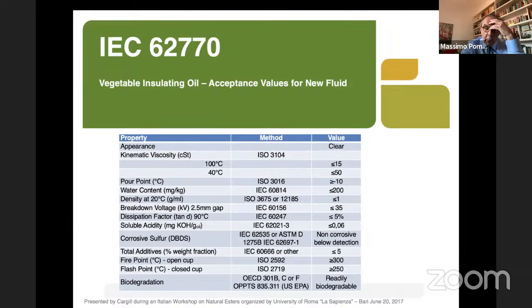Indeed, the breakdown voltage, as measured by a standard IEC 60156, is not so important, because this number depends not mainly from the liquid itself, but depends from water dispersion which you have in your liquid. Then is the dissipation factor and other property. And we are okay. It's a focus on this number.